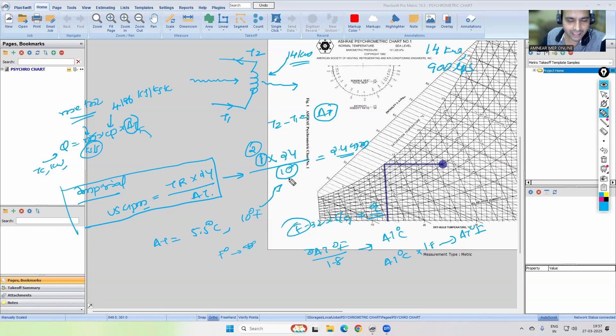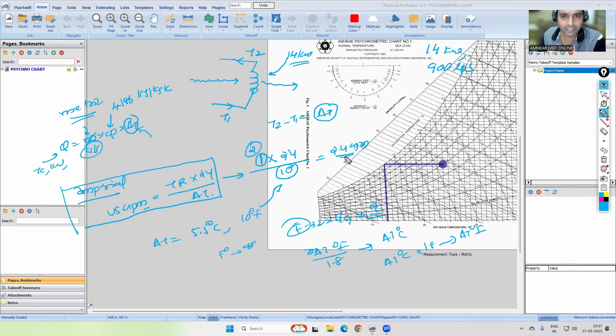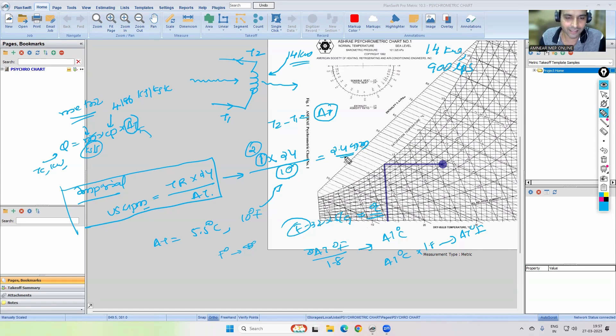This delta T is not fixed — it is fluctuating. If it varies, you will not get the same 2.4 GPM value. So 1 ton of refrigeration does not always require 2.4 GPM of chilled water flow. Sometimes we might require less than that.